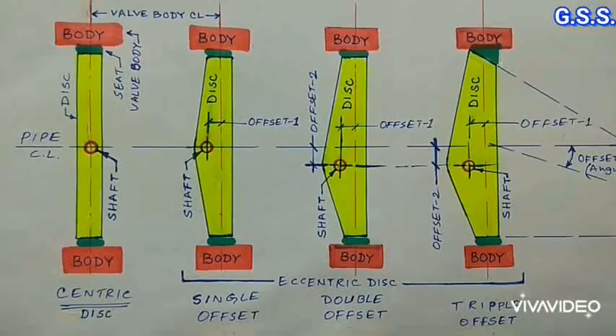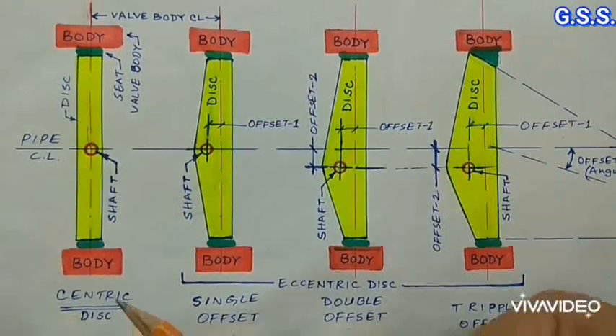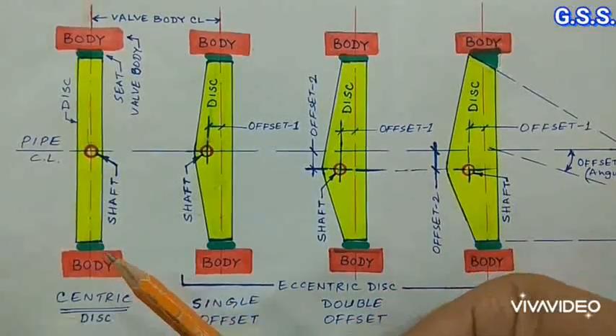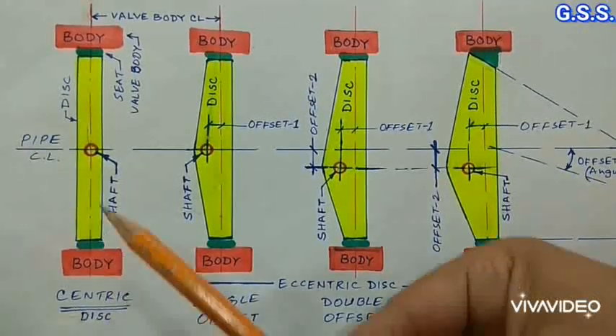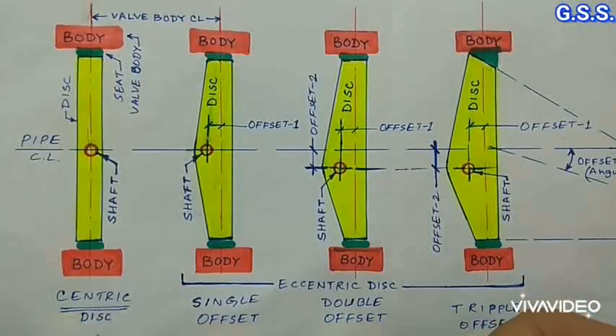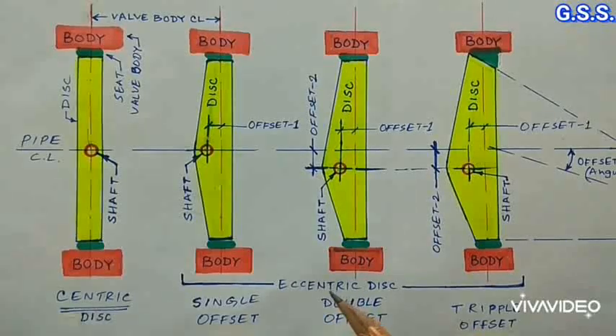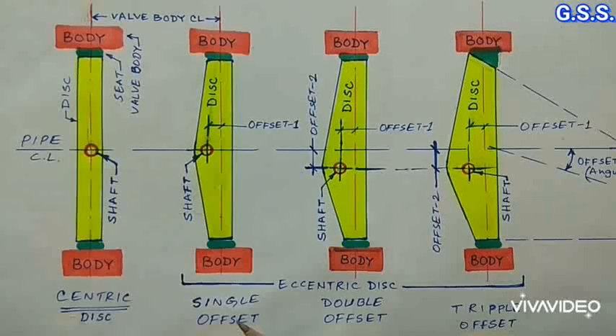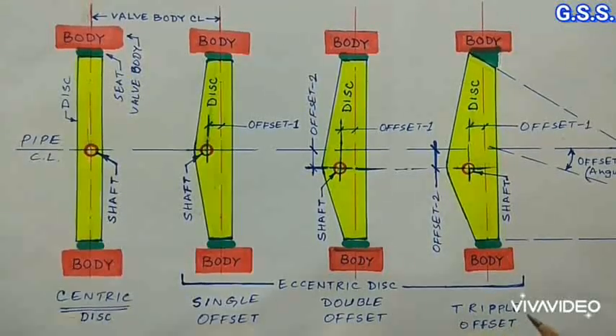This is top view of various types of butterfly valves. Red color is valve body, yellow color is valve disc and green color is valve seat. As per shaft and disc configuration, butterfly valves can be of centric that means concentric type and eccentric type. Eccentric type can be of three types, single offset type, double offset type and triple offset type.